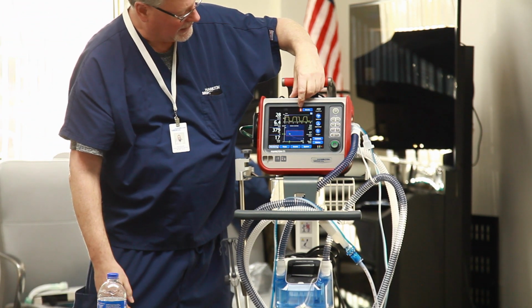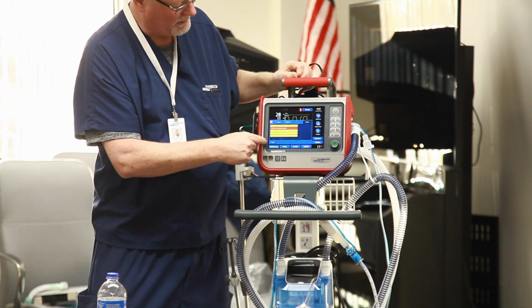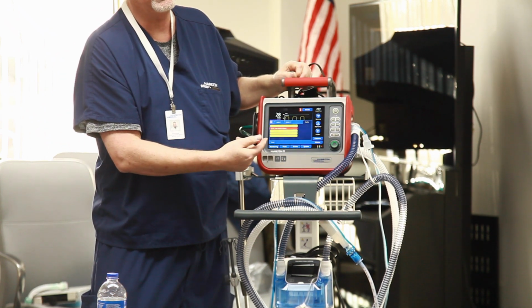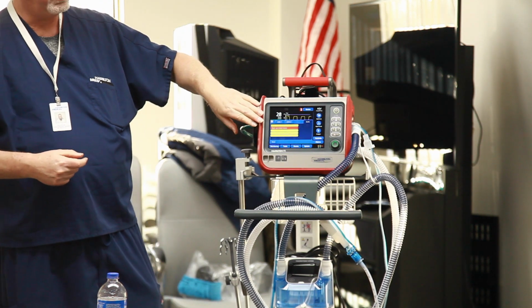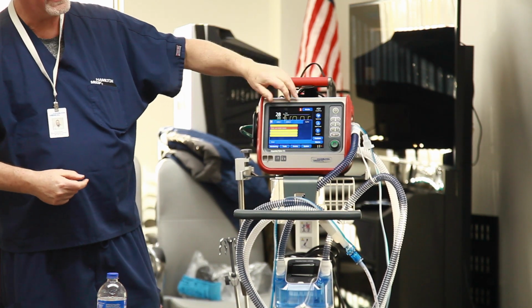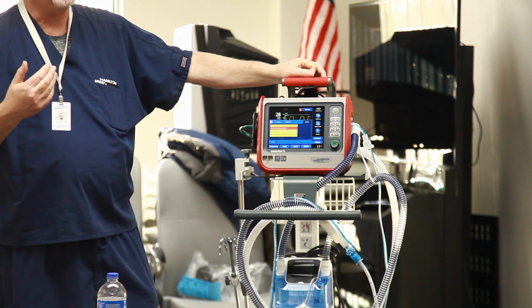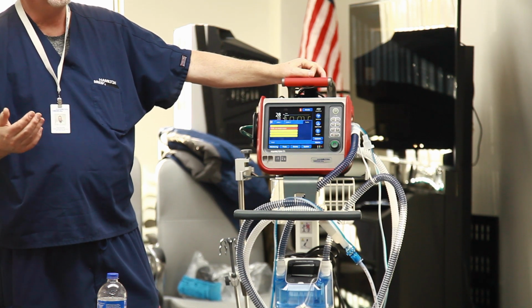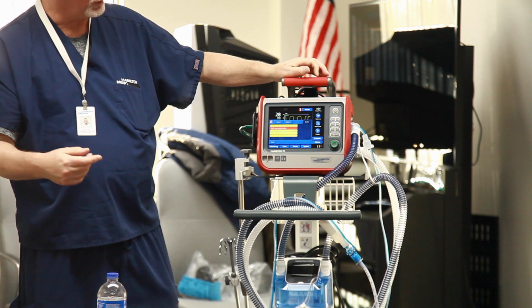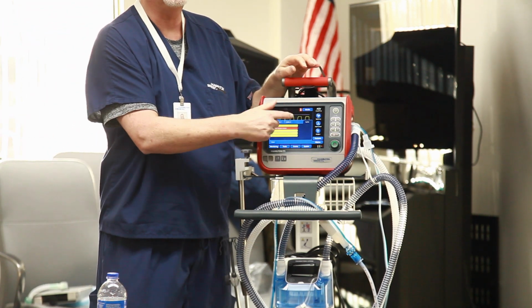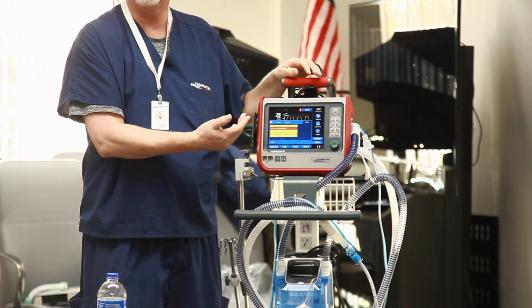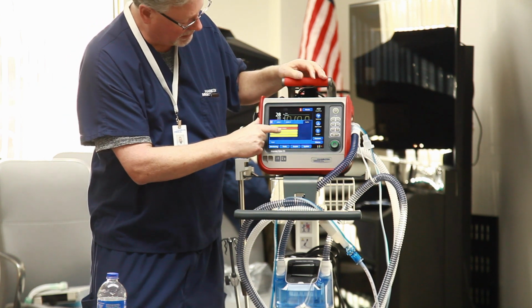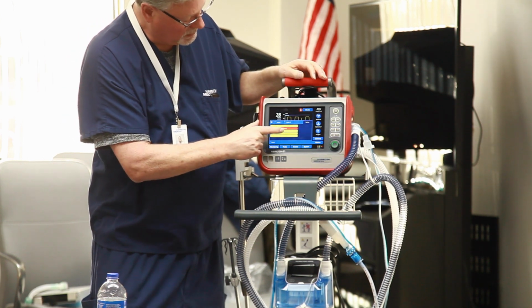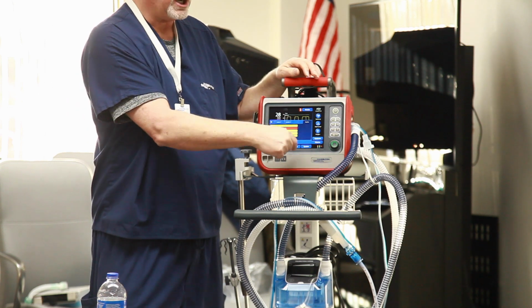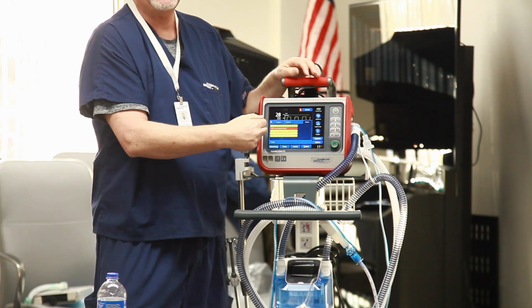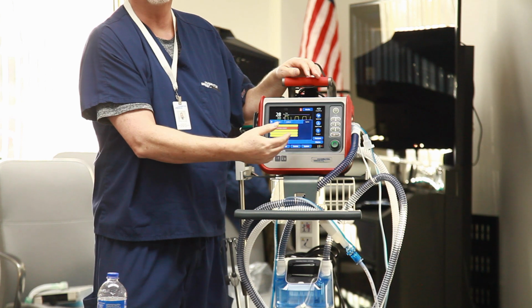There's another tab that you can look at. You can push the little icon here, and that'll have all the alarms that were going off since I reset it. This buffer window from this icon is a cool little place, because I'm telling you something that you don't have right now. But when they come to change the software, you're going to have a way to look at that alarm and understand what it means. If I push that alarm, like say low tidal volume, it would open up a little card here, tell me how it's defined, and then maybe give you a couple of troubleshooting ideas.